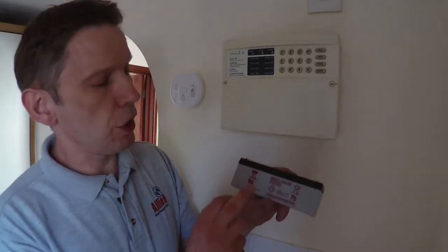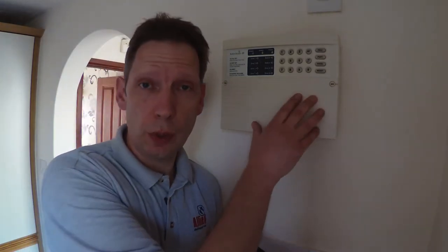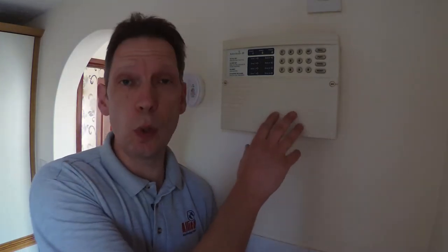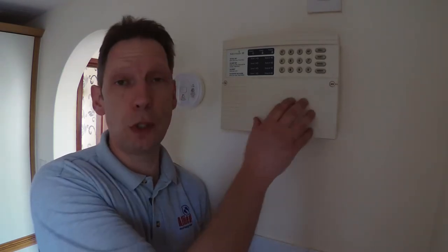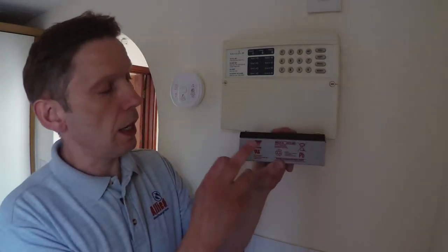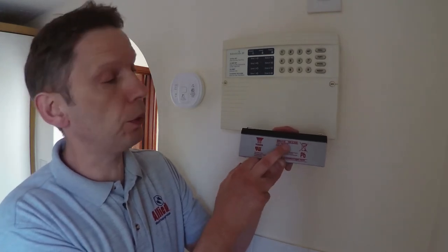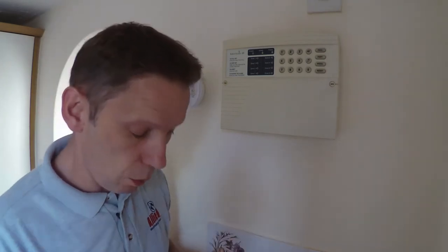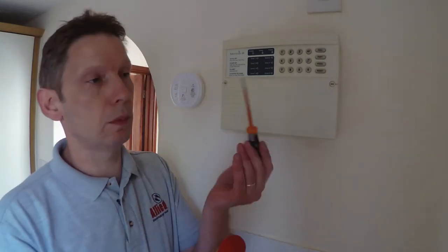So what's required to replace the battery in the alarm panel? Firstly, you'll need a battery. We suggest you get a like-for-like replacement. If your intruder alarm has been professionally installed, the battery will have been calculated to last a certain amount of time for your system. This particular one is a YUASA, which is a good quality battery — 2.3 amp-hour, 12 volt.